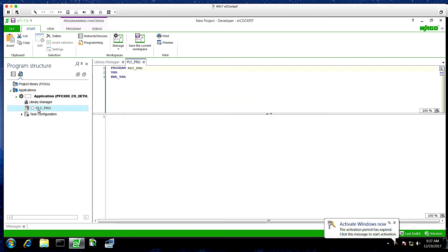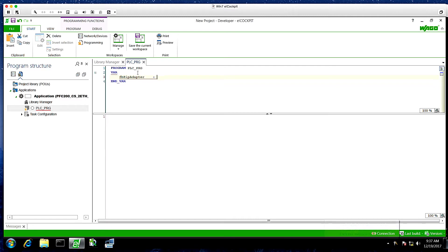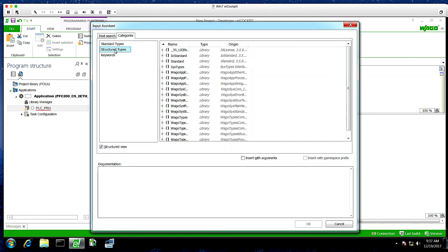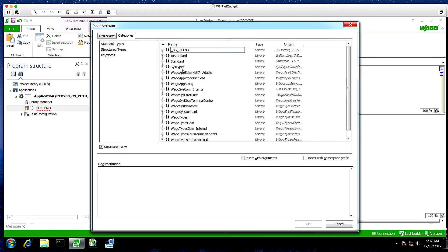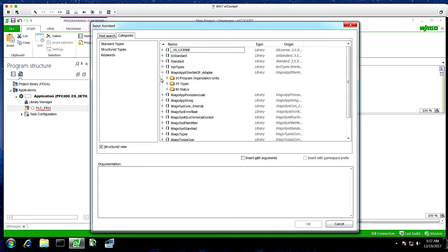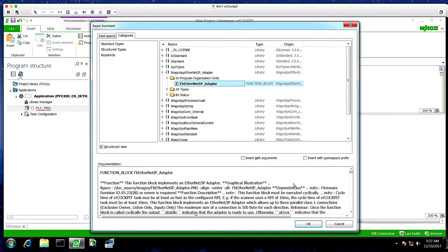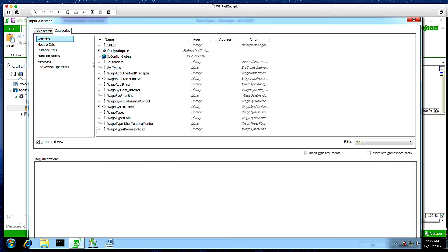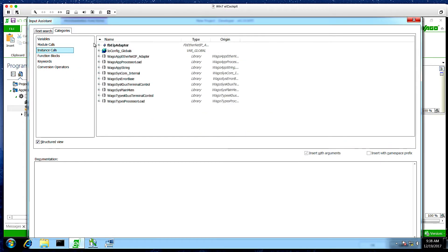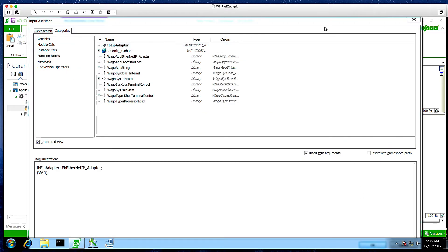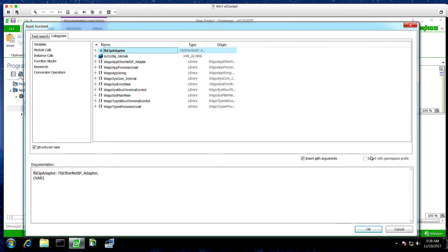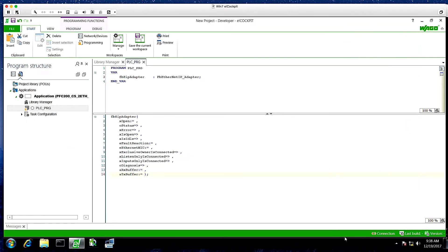Next, we're going to create an instance of the function block. We're going to call this FB_EIP_adapter. And we're going to search for the object type, which you'll find in the input assistant. Then we'll go ahead and call this instance in our programming window by using the input assistant again and going to instance calls. Resize our window. Click OK. And it will add all the fields.